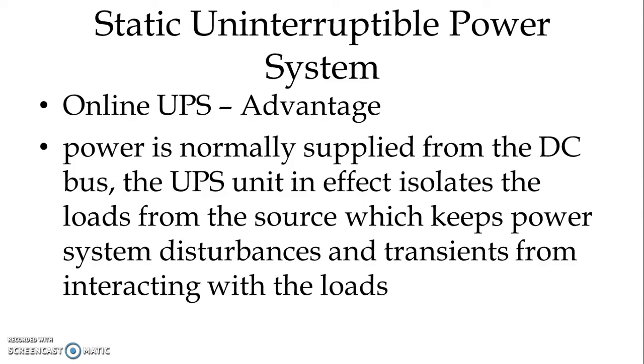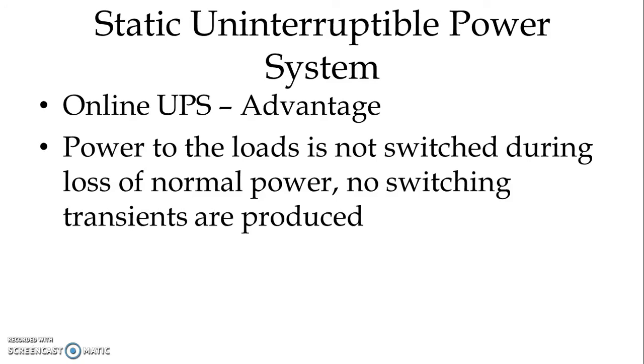Our inverter is always connected to the DC bus, and we give supply through the DC bus and inverter to the load. So normal transients or any power frequency disturbances do not affect the load. Power to the loads is not switched during loss of normal power. No switching transients are produced. In case of offline UPS, we have switching from AC power source to DC power source within half of a cycle, but again switching transients are produced, and that can affect the load.